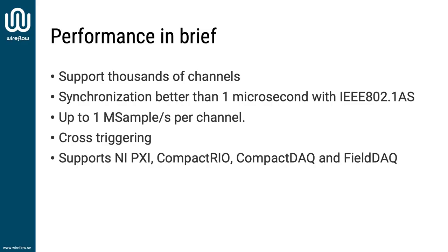We have a time synchronization of better than 1 microsecond thanks to the use of IEEE 802.1AS, which is the time synchronization part of TSN networking. We support up to 1 megasample per second per channel, and we also support cross-triggering, meaning that a logger node can trigger another node. And we can support the NI platforms PXI, CompactRIO, CompactDAQ, and FieldDAQ.